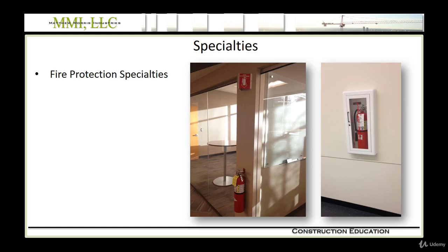And the quantity of fire extinguishers and the spacing between them is dictated by code, depending on the fire hazard. And they're usually noted on the general drawings at the beginning of the drawing set, specified by the architect. And fire extinguishers are either mounted on brackets, as you see on the left, or in cabinets, as you see on the right. Although local code will dictate this requirement, usually there can't be anything protruding more than 4 inches into a walkway, corridor, passageway, or aisle.